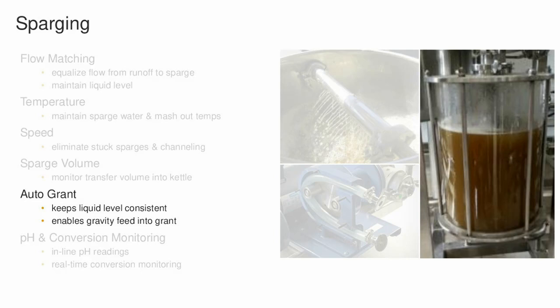So what can be done there is you put sensors in to monitor that liquid level, and then you're going to vary the speed of the pump that's pumping out of the grant. So what we end up doing is we put two floats in there. One is a high level, one is a low level. So what happens is as it fills up, the grant will trigger that low level and that'll turn the pump on automatically, which is a nice feature because you do not want to run that pump dry. So in addition to getting a nice flow, you have to be careful. If you run the pump dry, you're going to start destroying and wearing out your seals. So having that low float to have it turn on automatically is a nice setup.